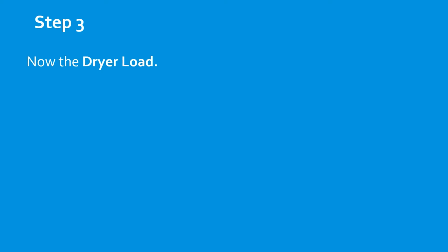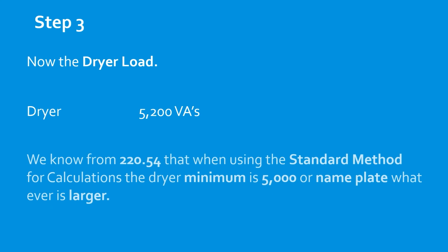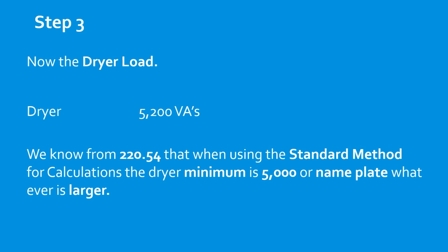Now do your dryer load. Our dryer's 5,200 VAs. We know from 220.54 that we have to use the 5,000 minimum or the nameplate rating, whichever's larger.